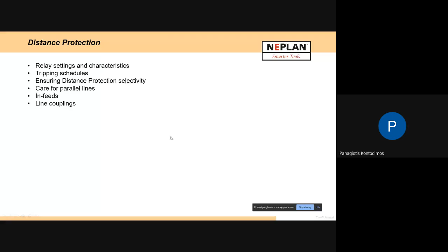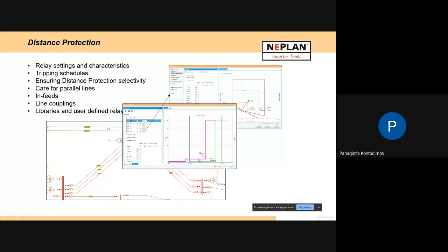Same is for distance protection, for transmission networks, where we have transmission lines and we use the distance protection relays to make the distance protection coordination, to ensure that the zones are well set in order to have selectivity, because there are some rules on how the settings should be and which relay should trip first according to the selectivity.